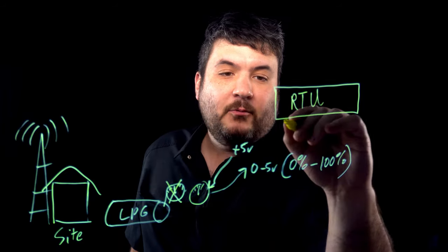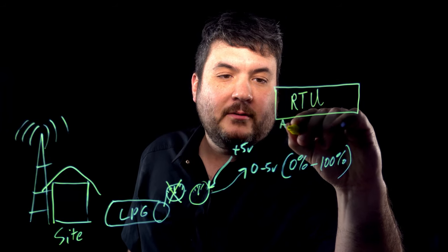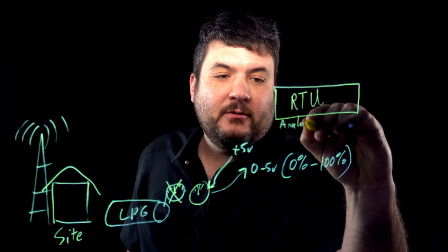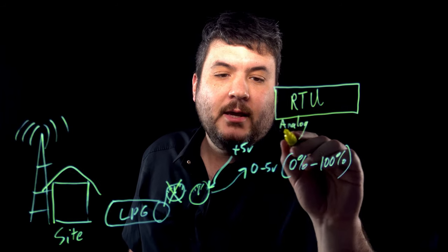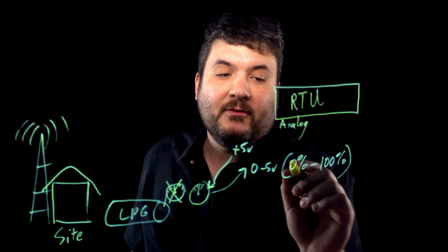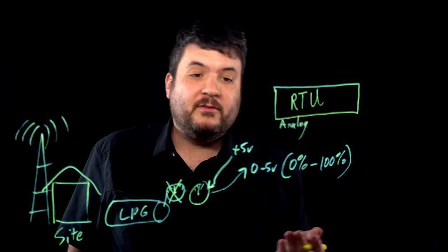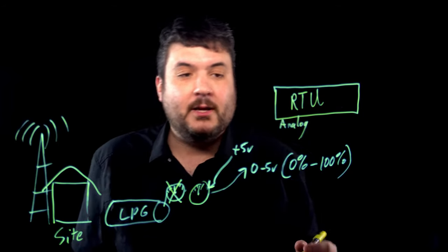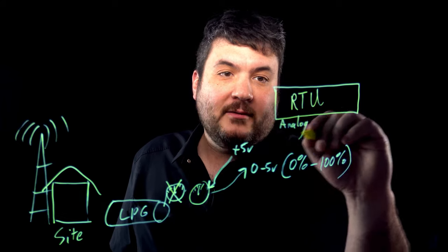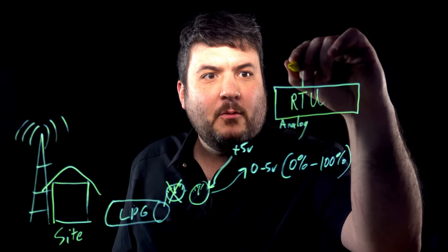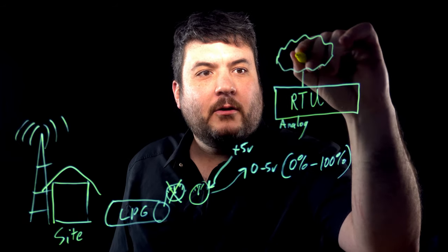So, what's going to happen is this is what we call an analog input. You're going to supply power to it and then it's going to feed you back. You're going to measure that voltage. And the RTU should be smart enough to say, okay, 3 volts. That must be 60% or whatever the reading is.